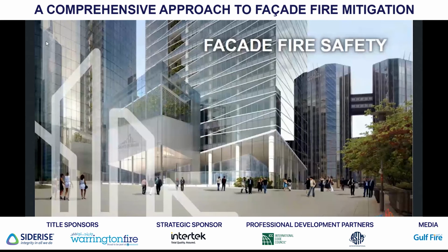With the recent introduction of combustible insulation in facade systems, Nada will highlight the fact that the current code is not addressed for all system types and will discuss the limitations, namely, 1. EU classification is more suitable for characterizing and classifying facade components. 2. Some of the sections in the code do not differentiate between types and heights of buildings, which is key in assessing the criticality in terms of fire performance. 3. Some of the fire propagation tests listed on the code are easy to pass compared to more stringent ones used for high-rise buildings, for example, BS/ISO.